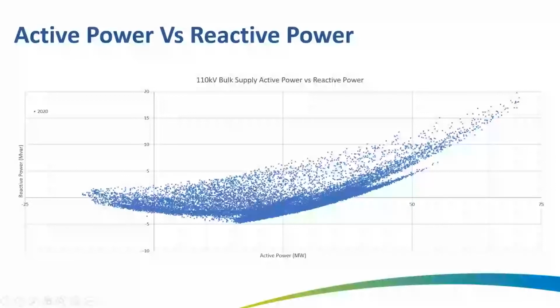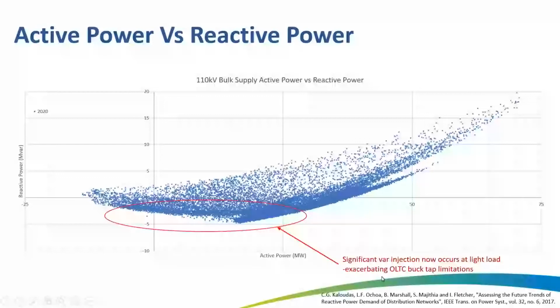And the other thing to note, of course, is that we've now got significant reverse flows happening. And we've also got a significant period of time when the reactive power is capacitive. That creates additional challenges for managing voltage and exacerbates our buck tap limitation. All of our power transformers have typically been designed with OLTCs to support peak load, but the amount of buck taps they have to pull down voltage at minimum demand is somewhat limited, and that becomes even more of a challenge when you add capacitive flows that also push up the voltage.